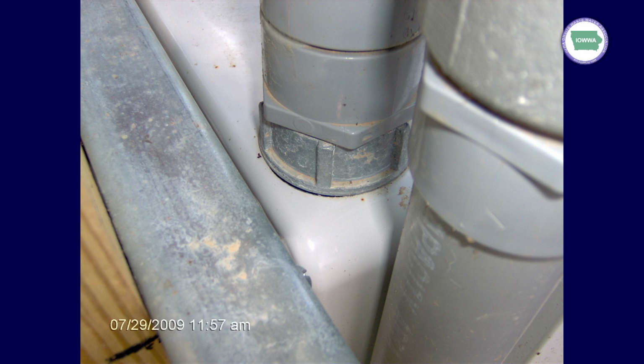liquid into the panel. And there's an example of a hole that was put into the top of the panel, and then they run a conduit hub down into it with no gasket, no sealing material, and also it's kind of hard to tell from this picture, but the hole that they drilled is a little bit bigger than what the conduit fitting required. So guess what happens? You're going to get a leak there, I guarantee it.